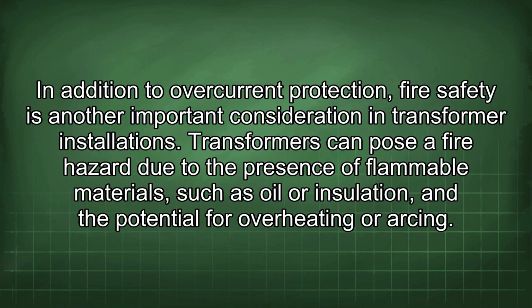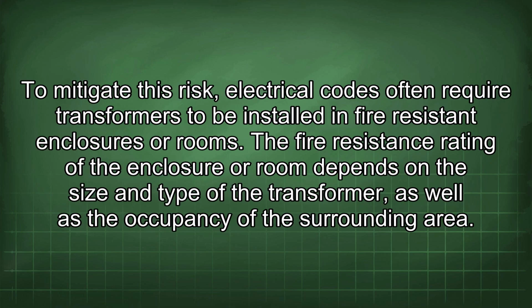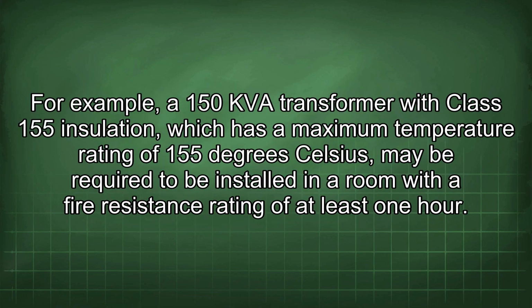In addition to overcurrent protection, fire safety is another important consideration in transformer installations. Transformers can pose a fire hazard due to the presence of flammable materials such as oil or insulation and the potential for overheating or arcing. To mitigate this risk, electrical codes often require transformers to be installed in fire-resistant enclosures or rooms. The fire resistance rating of the enclosure or room depends on the size and type of the transformer, as well as the occupancy of the surrounding area. For example, a 150 kVA transformer with class 155 insulation, which has a maximum temperature rating of 155 degrees Celsius, may be required to be installed in a room with a fire resistance rating of at least 1 hour.